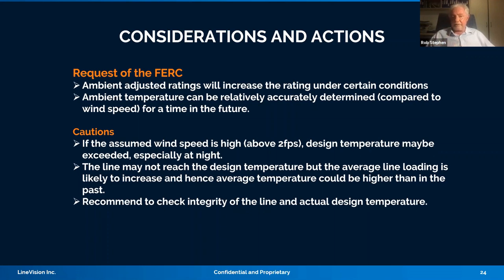Lines can actually have their thermal rating increased if you've got a very low ambient temperature and wind speed. You can go up to twice your static rating in certain cases, but you'll never do that on substation equipment, so you've got to be aware of your limitations there. With real-time monitoring systems on a line, we found the average increase is around 10%, but it can range from lower to quite high above, especially with high wind speed and low ambient temperatures.